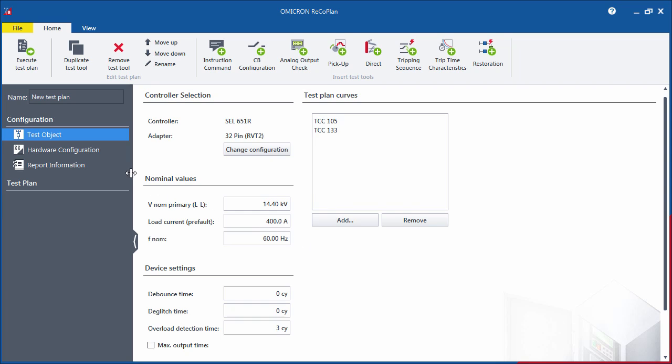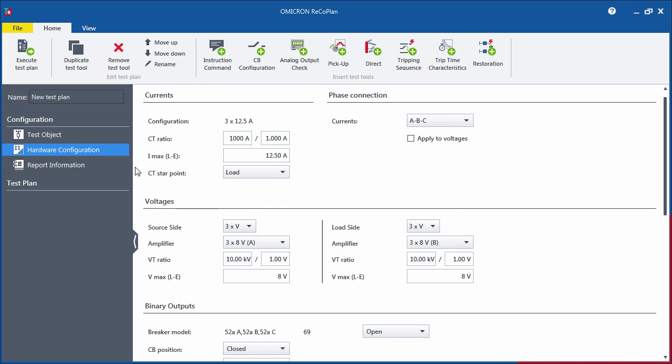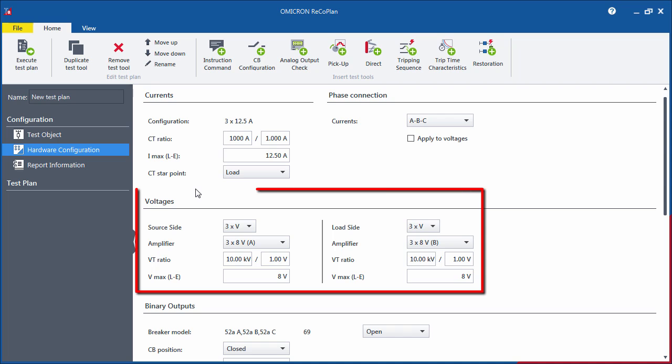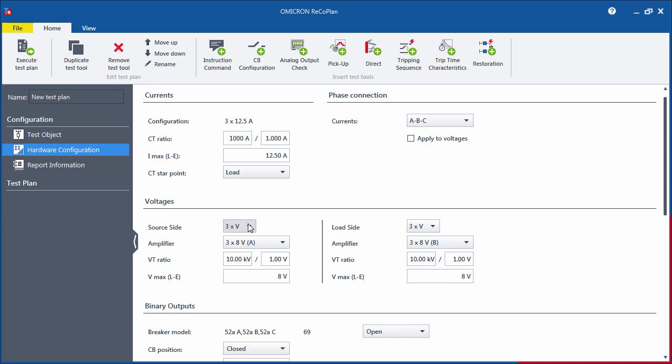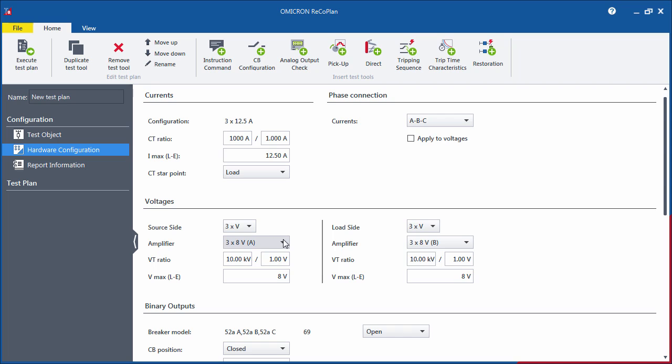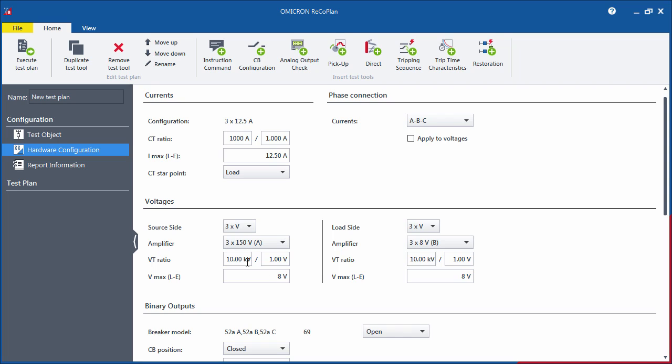The parameters in the hardware configuration are set to default values according to the adapter and controller selection in the test object configuration. Only the voltage selection may vary depending on your specific configuration. For instance, you can deactivate the voltages for the source side and load side or specify different VT ratios and maximum voltages to match your configuration.